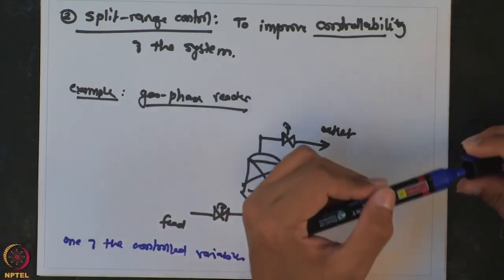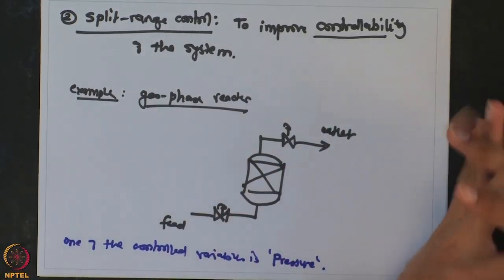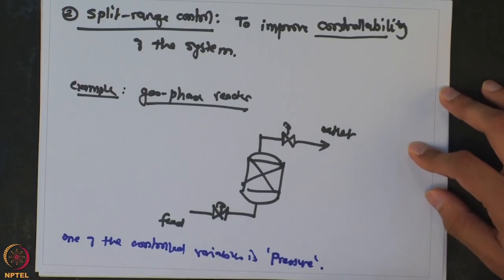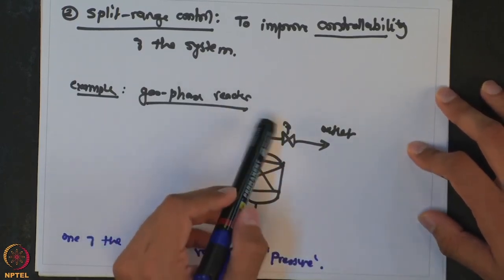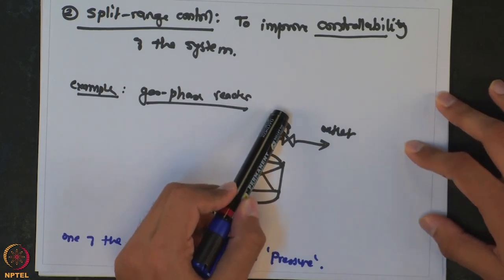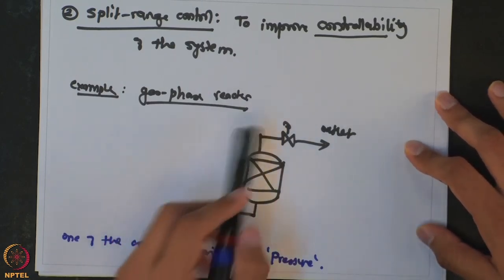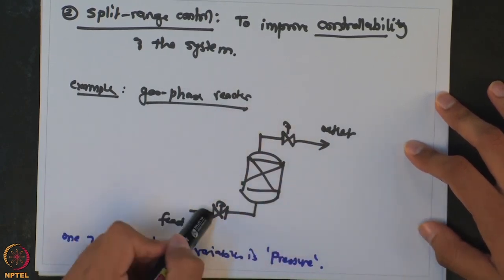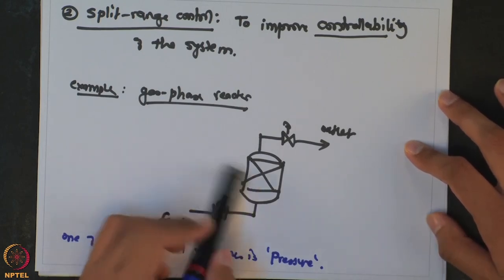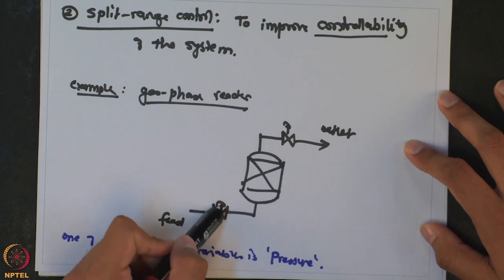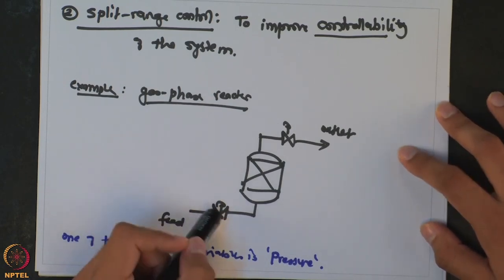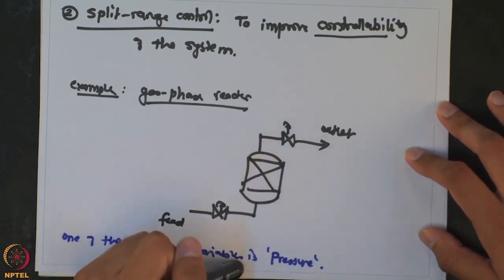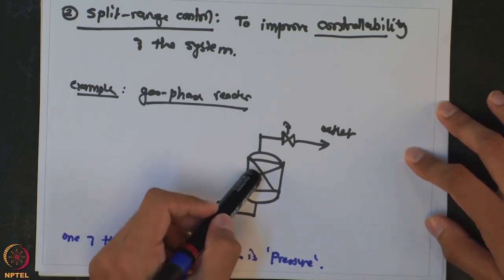Going back to last week's lectures, there are two primary options to control the pressure. One is by manipulating the outlet valve — if the pressure increases, open the valve more so more vapor goes out. Or I can use the feed valve such that if the pressure goes above the set point, I reduce the amount of feed going into the reactor.